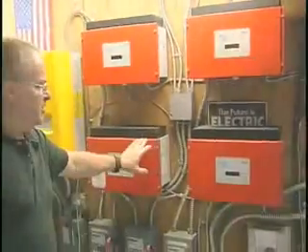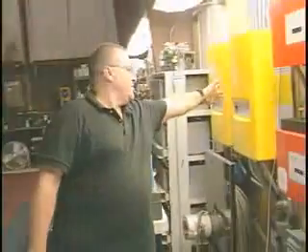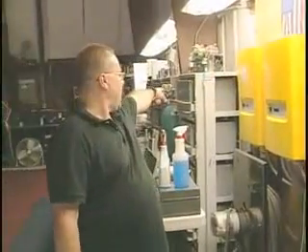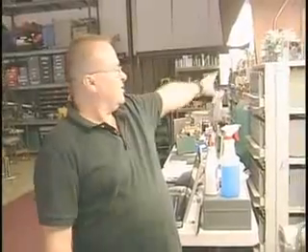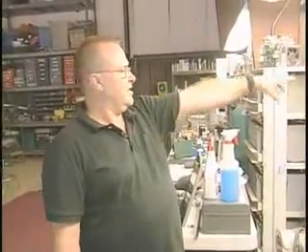The power comes down from the roof from the solar panels at 500 volts DC. That DC current goes through these four inverters here, where it's converted to 240 volts AC. From here, the energy goes into these two inverters, which pull energy from the batteries and provide power for the house. The two of them work together — so when there's not enough solar, it pulls off the batteries and puts out 220 volts up to the house.